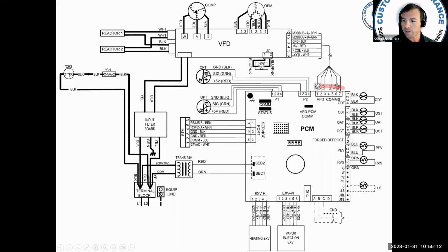Okay, so here's my VFD comms. I'm going to check for 5 volts DC between red and black. If I do not have it, then what I want to do is disconnect the VFD, okay, at the VFD J5 plug. If I disconnect it and the voltage comes back, then I want to check at the plug with it in my hand and make sure it's getting to the end of the wire. If you plug it into the VFD and the comm drops, then I probably got an issue with the VFD.